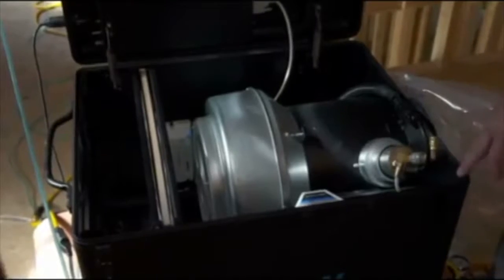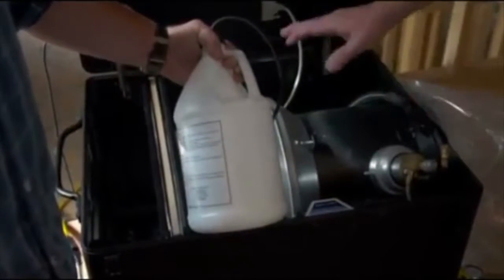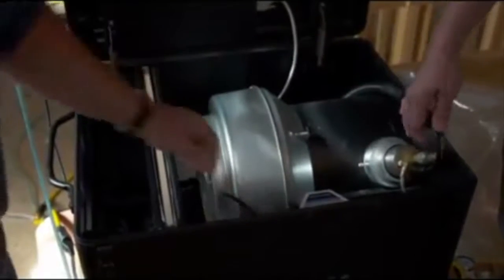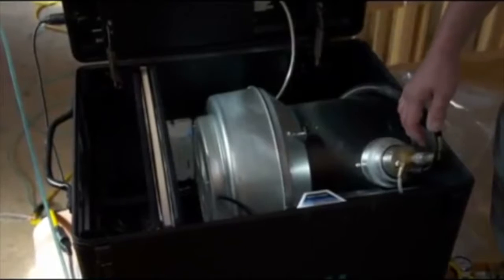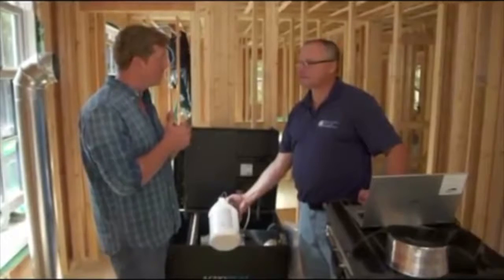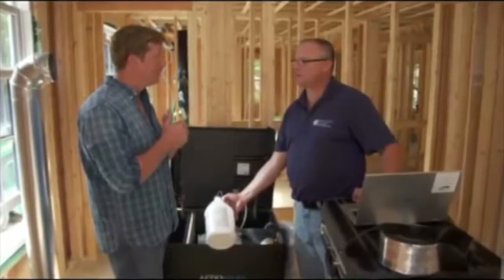My system uses a liquid chemical, the same chemical makeup as chewing gum. It uses a fan and compressed air to turn the liquid into an aerosol. We blow it through this duct and into the system. And so from the inside, as you try to blow this through there, as it tries to get out, it just locks onto all those leaks. It sticks to itself and plugs up all the holes.